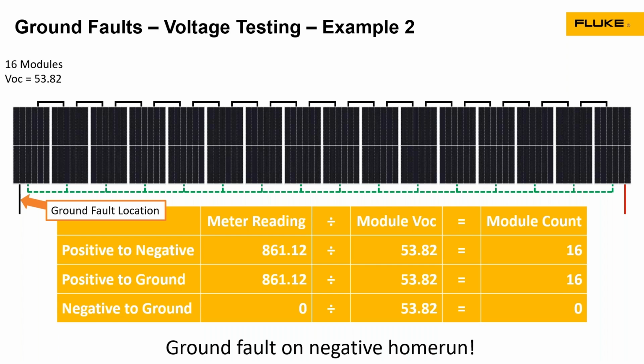Now, this type of situation is very common and can be very easy to miss because the readings that you get from positive and negative to ground are all numbers you expect. You expect to see 861 volts between the positive and the negative, not between positive and ground, but sometimes your brain forgets what you're testing and you miss that. And the 0 for negative to ground is what I want. So be aware of these. These can be harder to track down because the home run may be significantly longer, and it might be in conduit. I might have to go through and do some further analysis there.